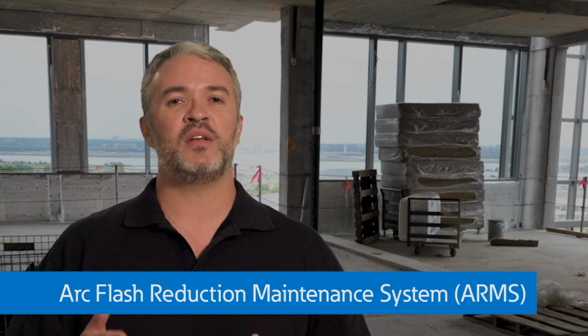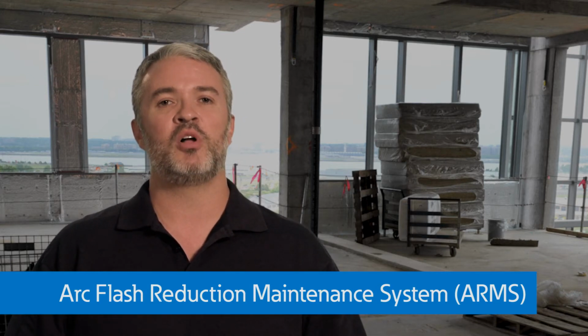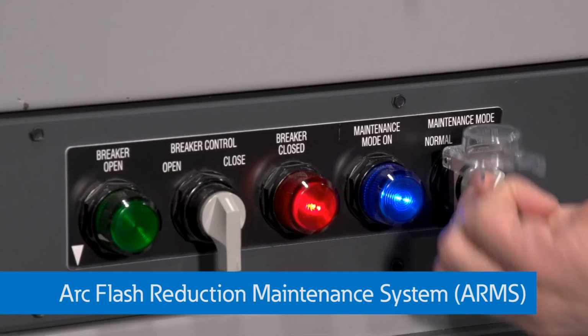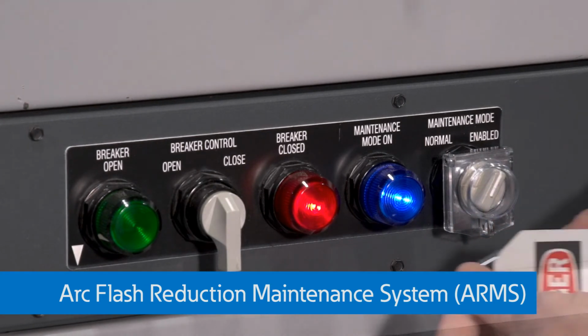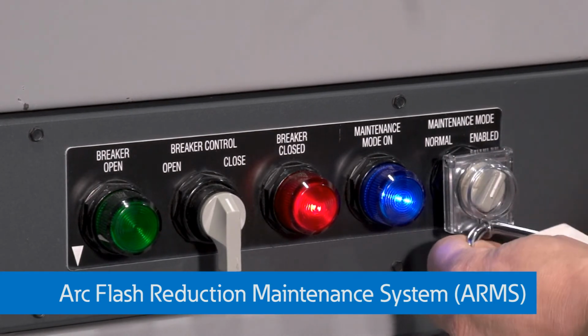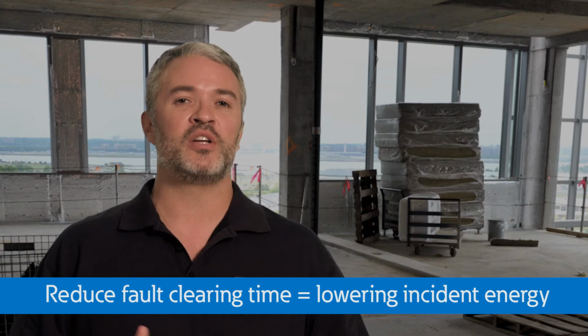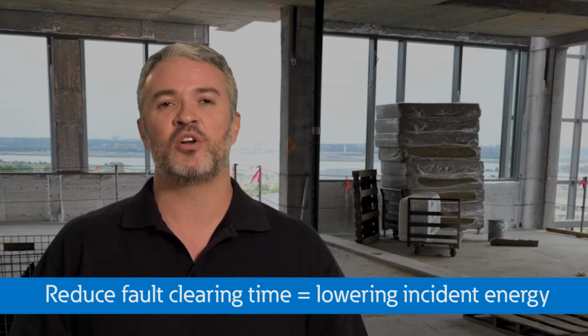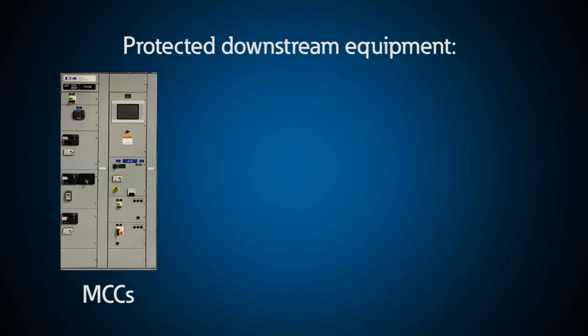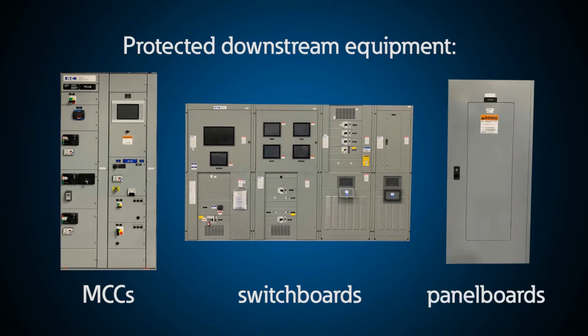Arc Flash Reduction Maintenance System, or ARMS, is available on low voltage power circuit breakers and many of our molded case circuit breakers. This system uses patented technology to reduce arc fault clearing time, lowering the available arc flash energy at the connected downstream equipment like motor control centers, switchboards, panel boards, and other equipment.